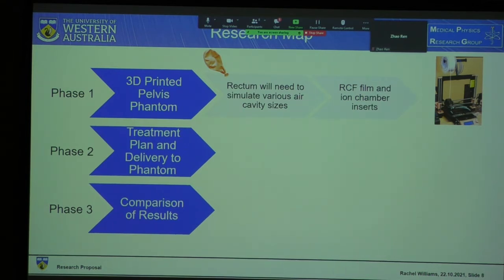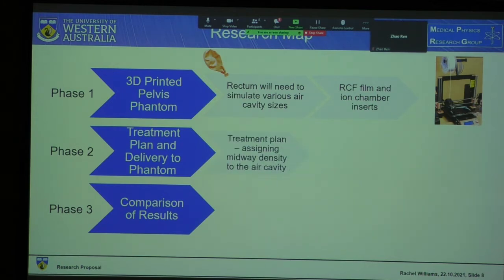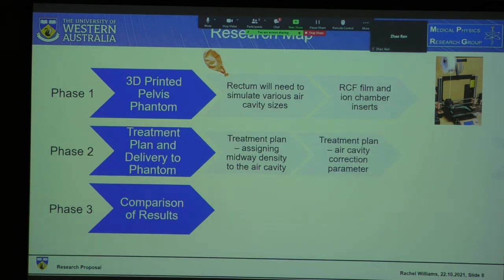Both radiochromic film and ion chamber inserts will need to be in the phantom, as the dose distribution will be measured by the film and the absolute dose by an ion chamber. The second phase is the treatment plan and delivery to the phantom. Treatment plans will be created by assigning a density midway between air and tissue to the cavity, and another using the air cavity correction parameter. Both will be delivered by a Varian Linac for various air cavity sizes.